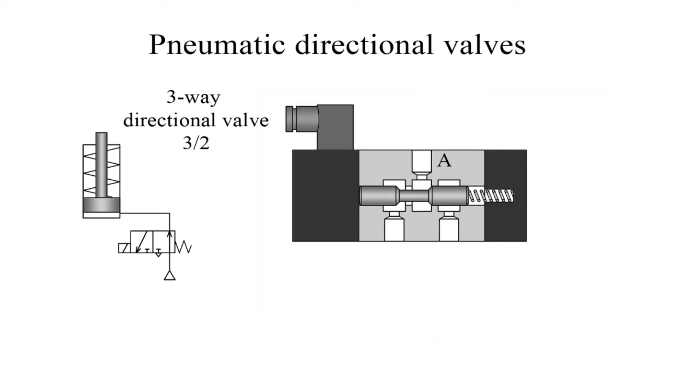Three-way directional valves are available in a normally open or normally closed operating configuration. This valve is normally open. Three-way valves are used to control spring return cylinders or other single-acting cylinders.